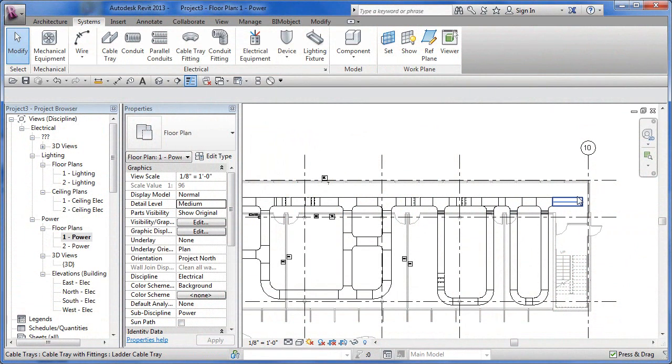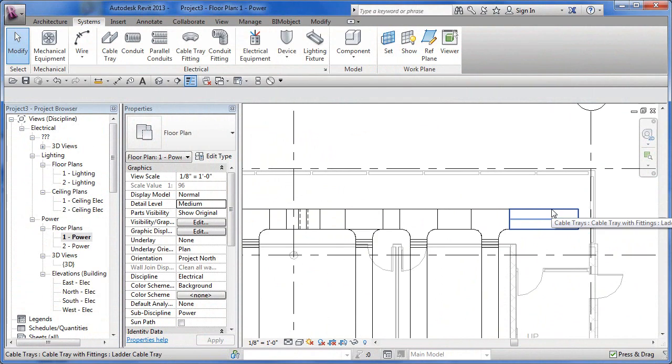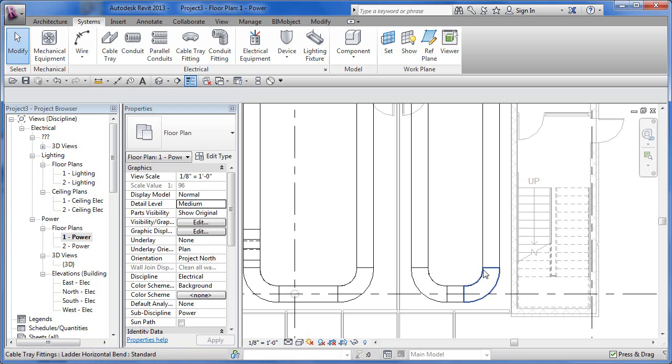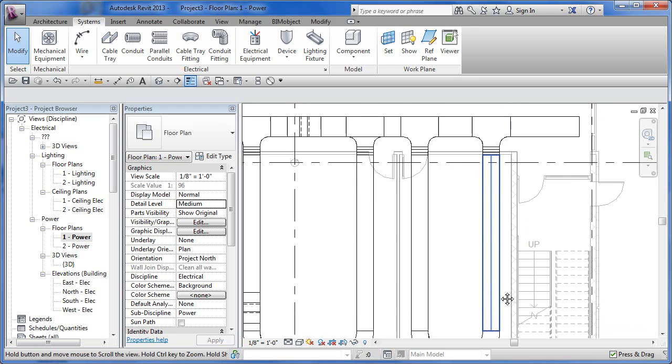Now, drawing vertical cable tray and ductwork, very much the same, is a little bit tricky because we always forget to anticipate the bending allowances. Like over here, we have a 30 inch, or just under a meter radius on these bends. And as you think of this as going vertically, the transition between this plane and then up over here has to be at least two bend distances with a little bit of fitting in between, and that goes for vertical as well.